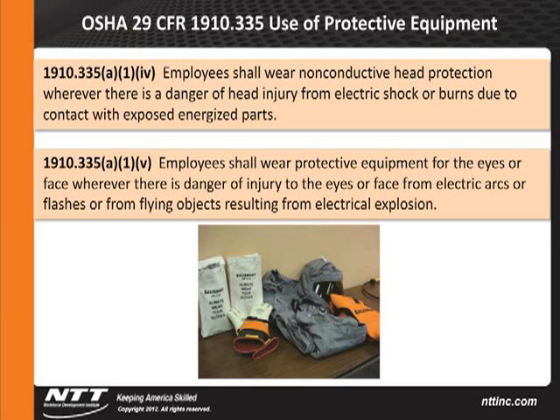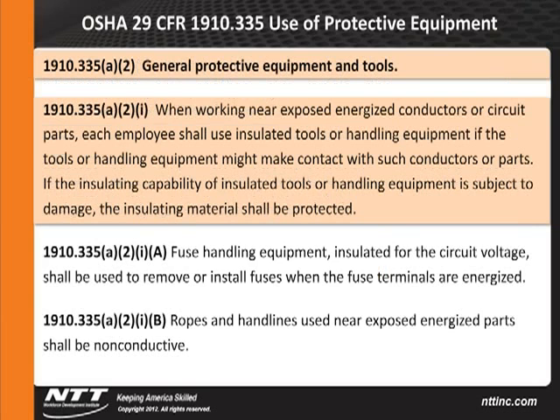As we continue to go on, when working near exposed energized conductors or circuit parts, each employee shall use insulated tools or handling equipment if the tools or handling equipment might make contact with such conductors or parts. If the insulating capability of insulated tools or handling equipment is subject to damage, insulating material shall be protected. Again, some type of a tool. And again, the industry has set forth standards for those types of tools. And I don't mean putting tape on a screwdriver or dipping them in a can years back that used to have the plastic dip in them.